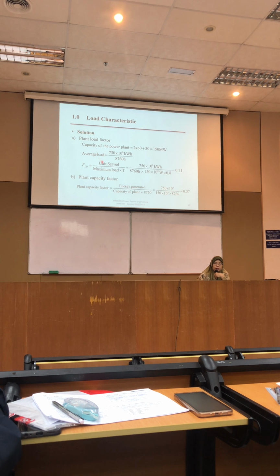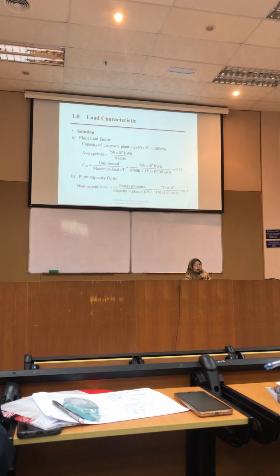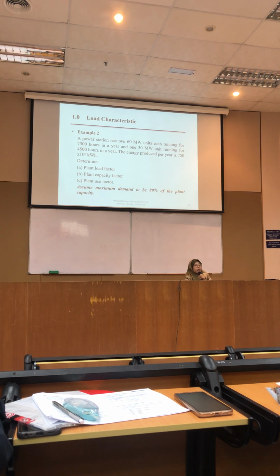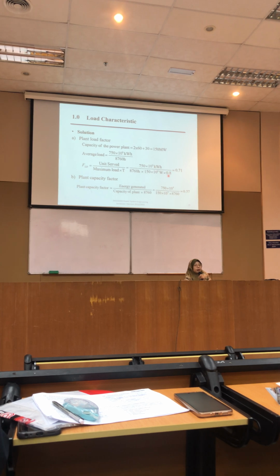So the average load will be the unit served, and then maximum load times the... Why 0.8 here, student? Because the maximum demand given in the question is 80% of the plant capacity, so we have to multiply with 0.8. And then the plant capacity factor is the energy generated divided by the capacity of the plant times the time. So we are going to get 0.57 for the plant capacity factor.